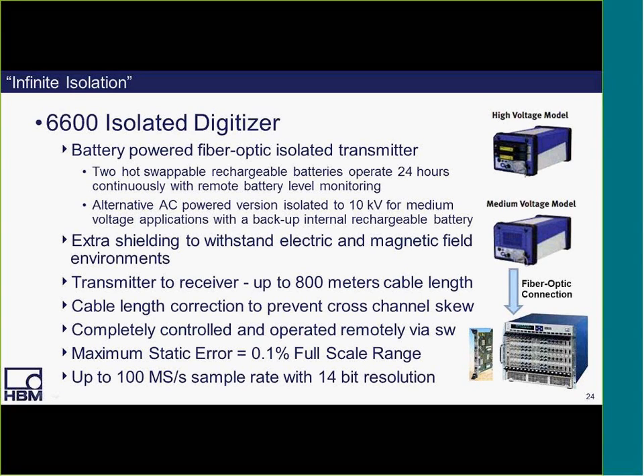Now, as an alternative solution, if you're measuring only up to 10 kilovolts in your particular application, there is an AC-powered version available, which has up to 10 kV isolation for medium voltage applications, and has a battery backup inside the system itself. So each of these high voltage and medium voltage models provides extra shielding to withstand electric and magnetic field environments, and the connection between the high voltage or medium voltage transmitter is achieved through a fiber optic cable to the receiver in a mainframe, which can be up to 800 meters away.